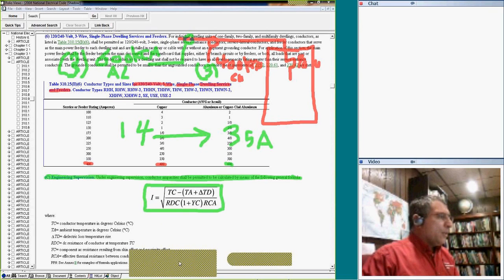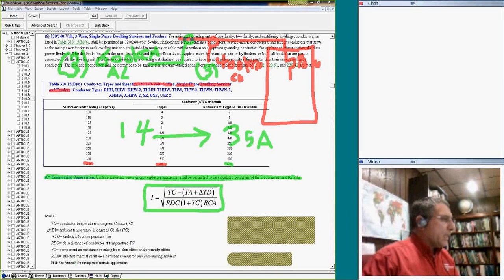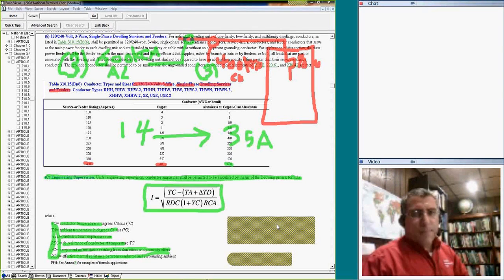The formula, guys, you wouldn't use it unless you're familiar with it, unless you have software that does it. It's all about temperature. So conductor temperature in degrees, ambient temperature in degrees, dielectric loss temperature, DC resistance at the temperature, component AC resistance resulting from skin effect and proximity effect, how close they are to each other, effective thermal resistance between conductors and the surrounding temperature. So you can see this is basically a thermodynamic equation that you're looking at. You don't have to worry too much about it.